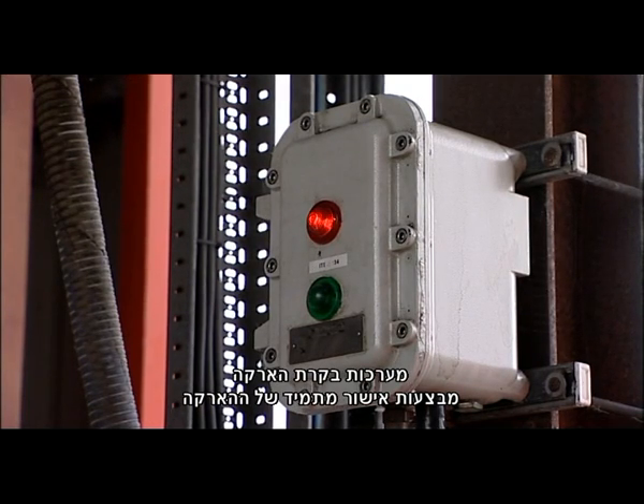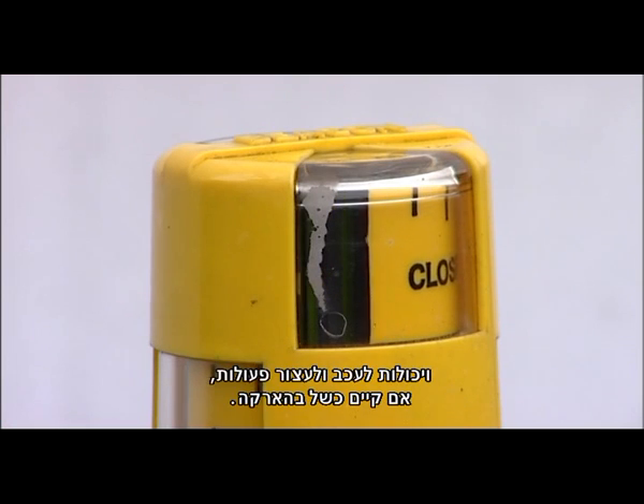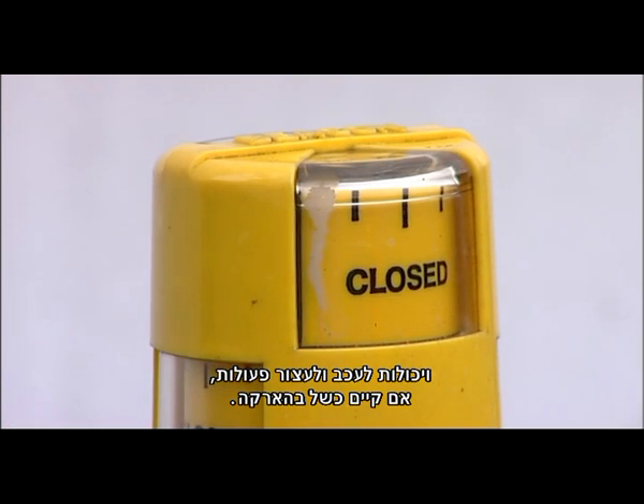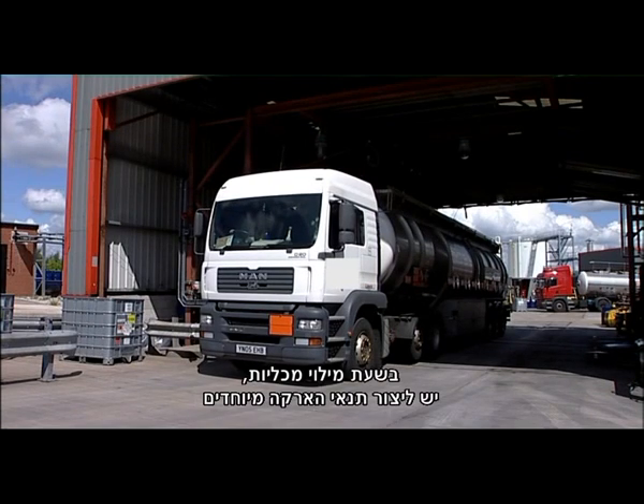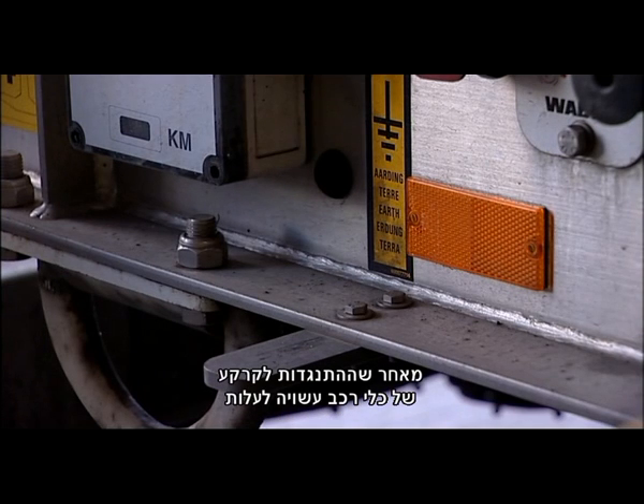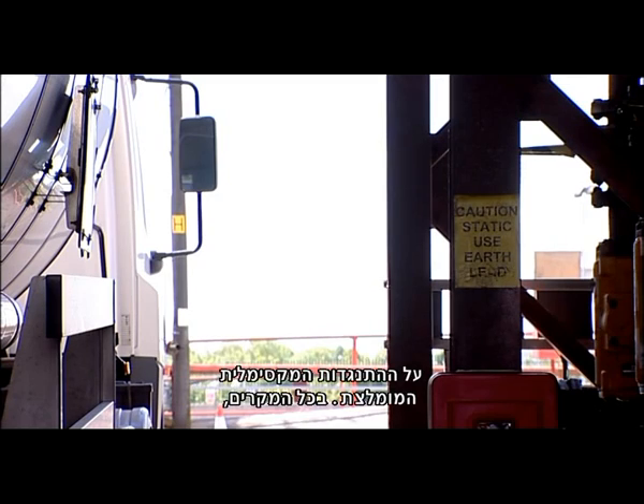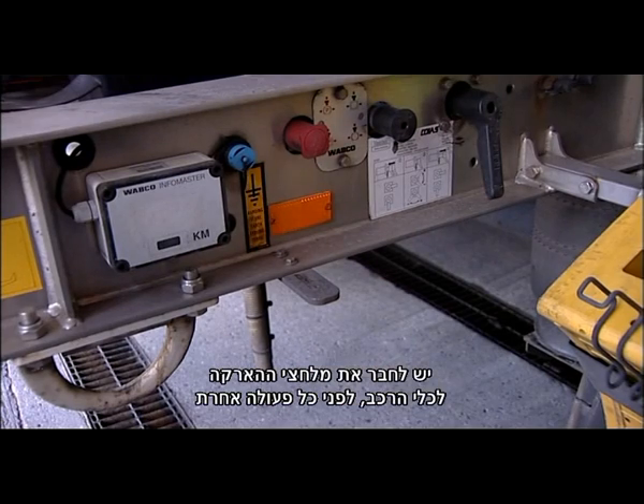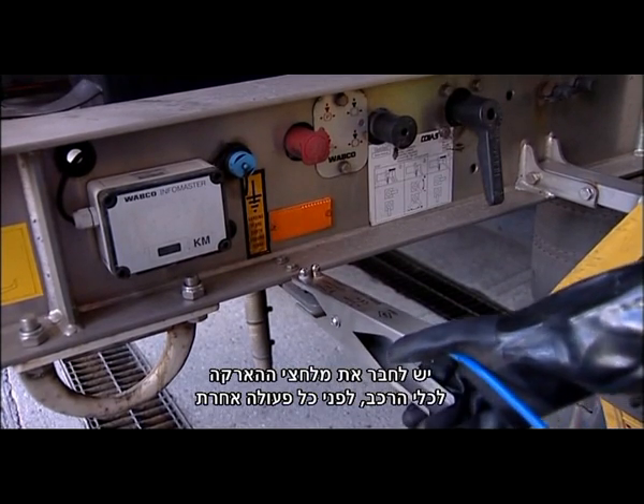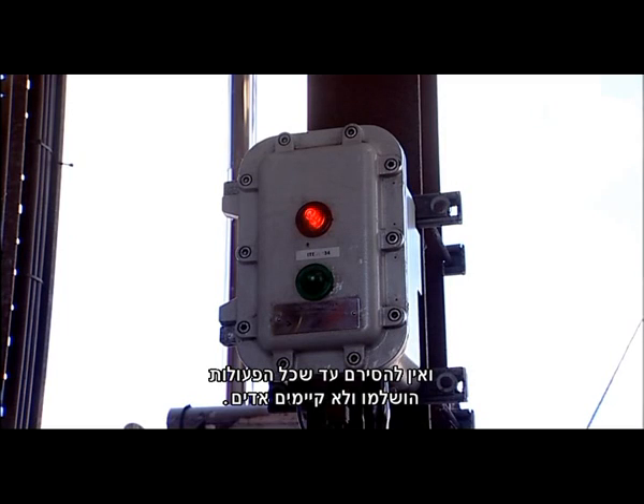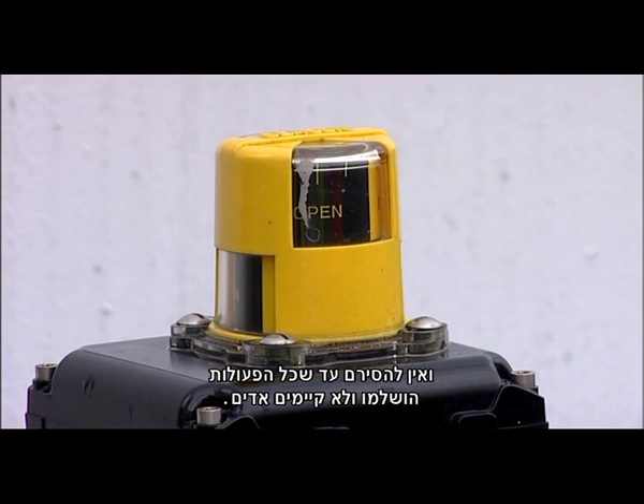Earth-proofing systems offer a continuous confirmation of earthing and can prevent and halt operations if there is an earth failure. When filling road tankers, special earthing conditions must be made, as the resistance to earth of a vehicle can exceed the recommended maximum resistance. In all instances, the earthing clamp should be attached to the vehicle before any other operation, and should not be removed until all operations are complete and there is no presence of vapor.